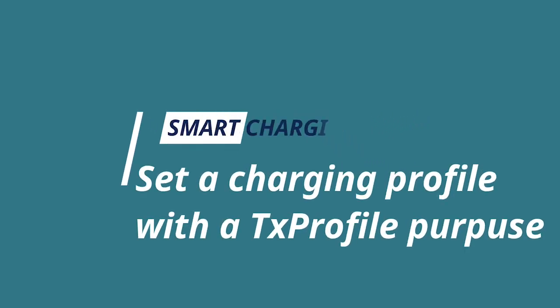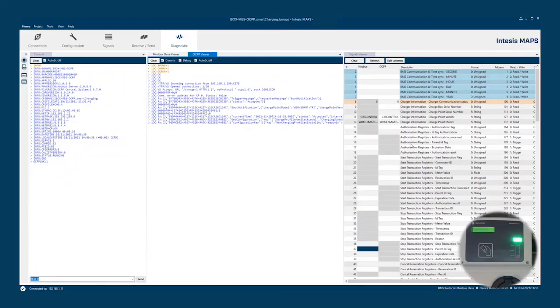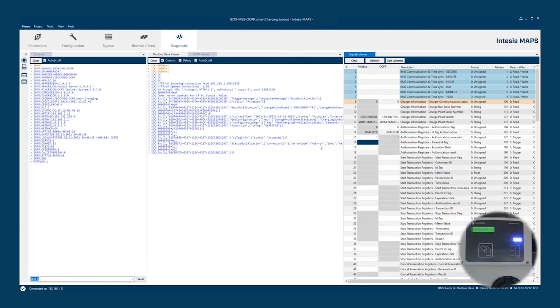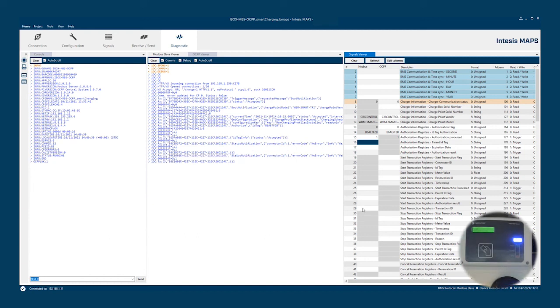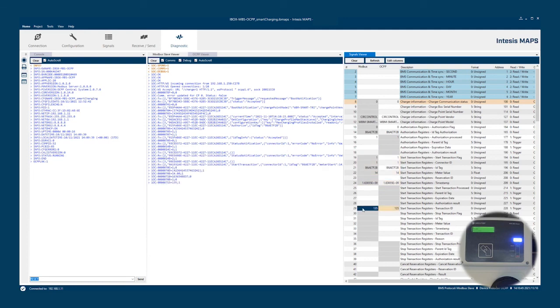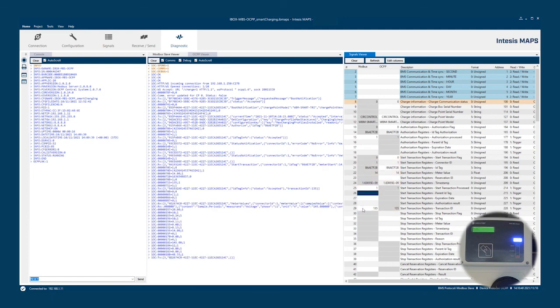Now we will be adjusting the charging power for this connector that is known as smart charging that allows to adjust the power provided by the charger at a specific point or set schedules to help with load balancing or increase or reduce the electric vehicle charging according with your building needs. We will again authorize a transaction after approaching the RFID tag as we did before using the same registers. We will now plug in the connector and process the start of the transaction once more. Just this time, we can assign a different transaction ID.